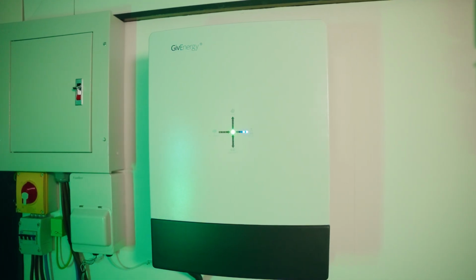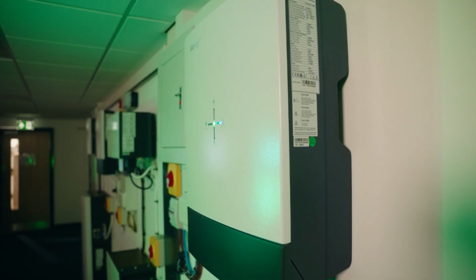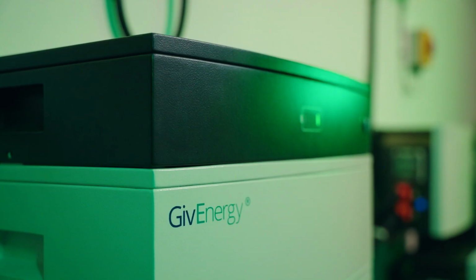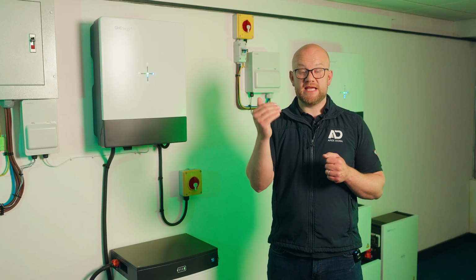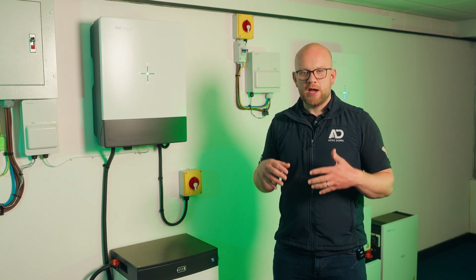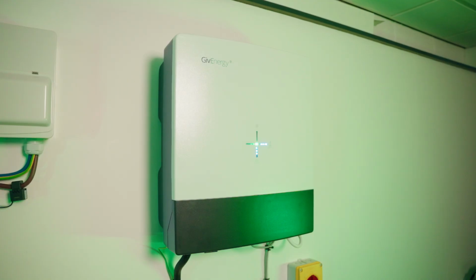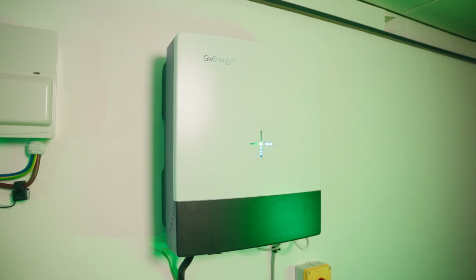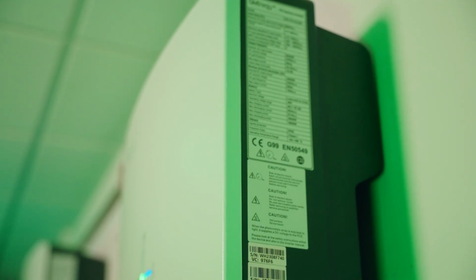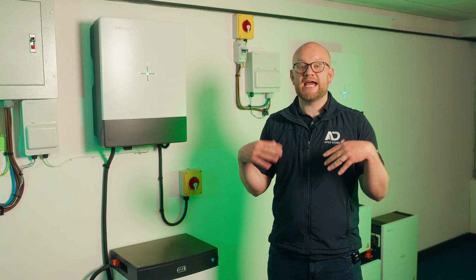With a bigger inverter, like this hybrid inverter with the stackable kit we've got here, there may be more requirements on you as the end user and your engineers regarding the national grid. If you've got a 3.68 kilowatt inverter or below, that's notified under something called G98, fit and notify, when you tell the grid.